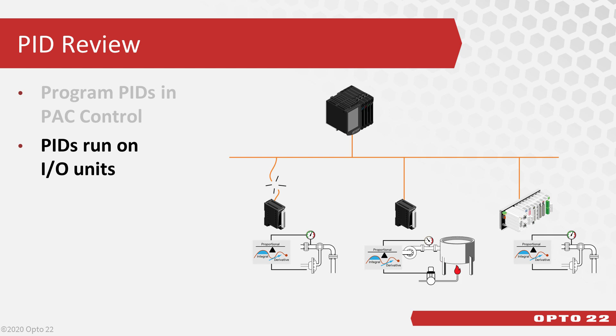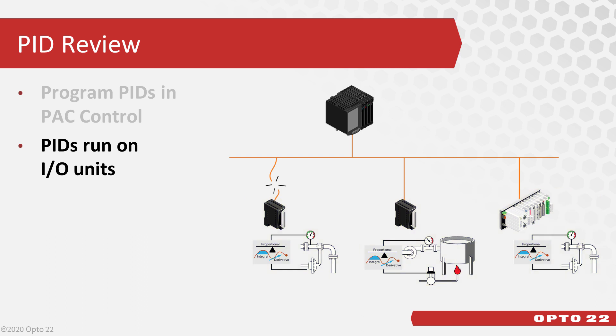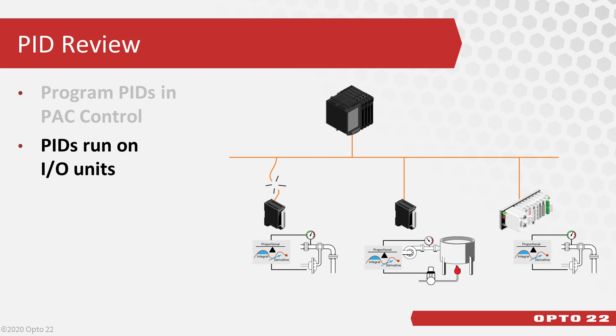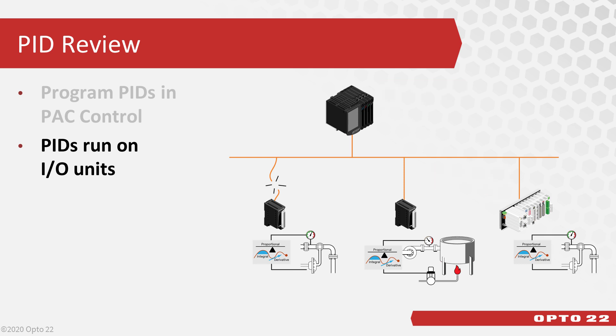Where you can see how that makes a difference is when you have remote IO units running PIDs. If communication to the controller is interrupted, like we see on the first IO unit, the PIDs on the remote unit keep running until the unit is powered off. You can have up to 96 PIDs running on groov EPIC IO and SNAP PAC IO units, and up to 4 PIDs on groov RIO units.